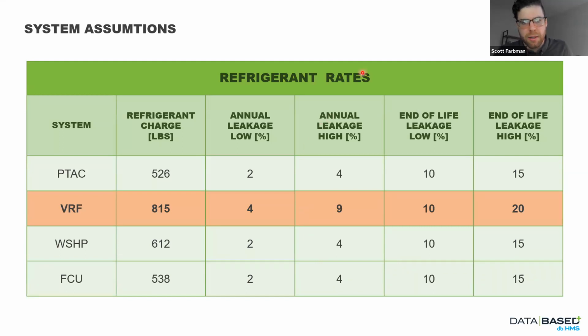So refrigerant rates, we're looking at a couple things here. We're looking at the total amount of refrigerant in the system. We're looking at how much that system leaks annually. And we looked at a low scenario and a high scenario to look at the variability there. And one area where we in the industry, the professionals, the researchers, the academics, et cetera, need to get better is really honing down on what this leakage rate is. Because if we look at VRF right here, on a low leakage scenario, it's 4% of its total refrigerant each year that could leak. On the high end, it could be as much as 9%. That's a lot, and that's a big difference. And we don't really know what the rule of thumb is right now. So keep that in mind for next steps in terms of research and technology.